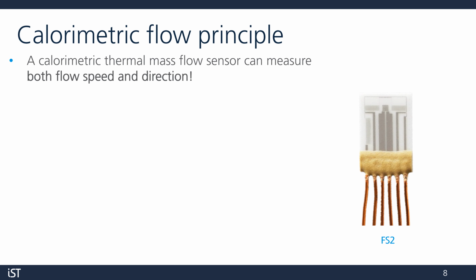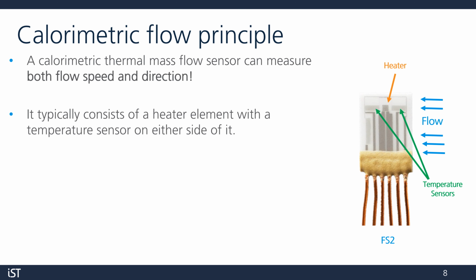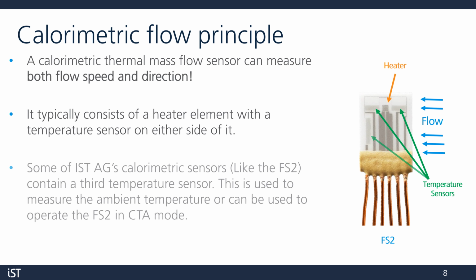If for some reason you'd like to detect both flow velocity and direction, we have another sensor called the FS2. This uses the calorimetric flow principle. It usually consists of a heating element with one temperature sensor on either side of it. Some of IST's calorimetric sensors, like the FS2, contain a third temperature sensor which can be used to measure the ambient temperature, or it can be used to operate the sensor in CTA mode like we do with the FS7.